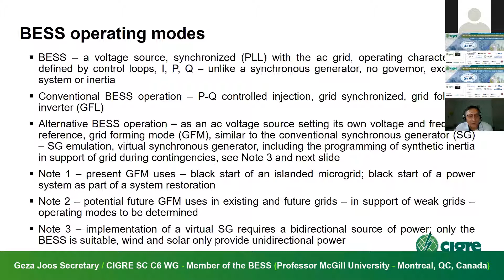What is being talked about very much these days is grid forming inverters, which are supposed to be similar to synchronous machines. They're virtual synchronous machines if you want to program them like that. The only problem is that there is no inertia to speak of. You can emulate an inertia with a battery energy storage system, but you have to program the function. So the present use of grid forming modes is islanded operation, as I mentioned, and there's a big talk about the future potential of grid forming inverters in systems where the amount of synchronous generation is going down, and particularly when you go to 100% renewables.